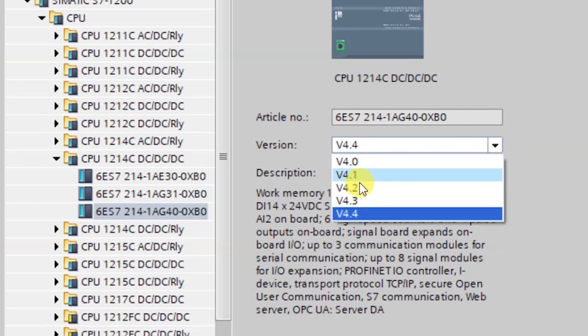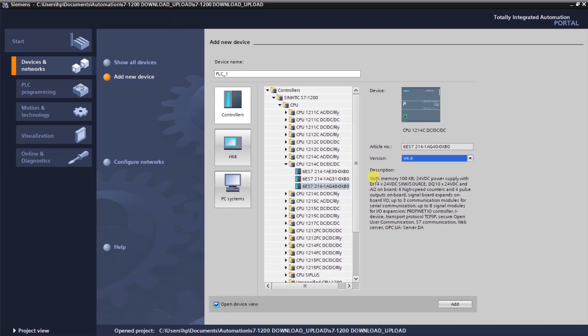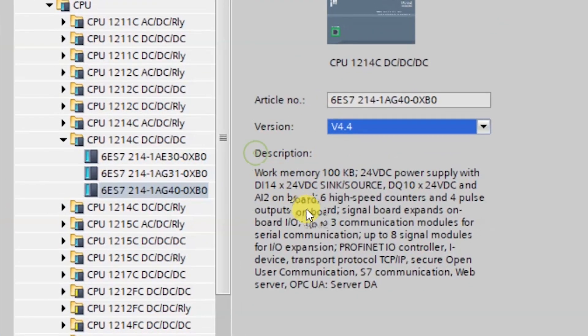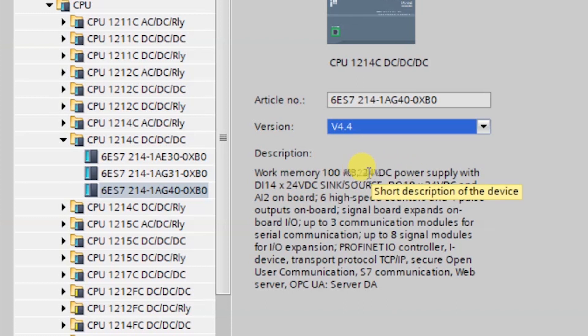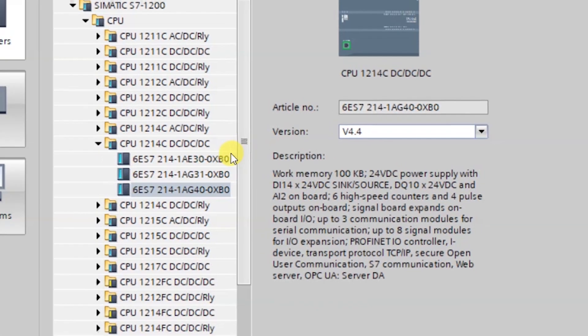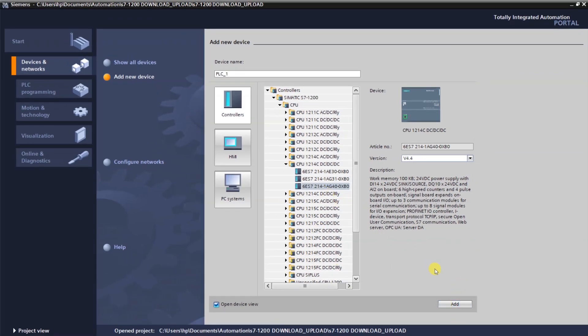We have a CPU 1214C DC/DC/DC and multiple controllers in this series. Check the catalog number written on the right face of the PLC — I have 6ES7214-1AG40. Select the version; V4.4 is the latest. The description shows it has 100KB work memory, 24V DC supply, 14 digital inputs, and 10 digital outputs of 24V DC. Click 'Add new device'.